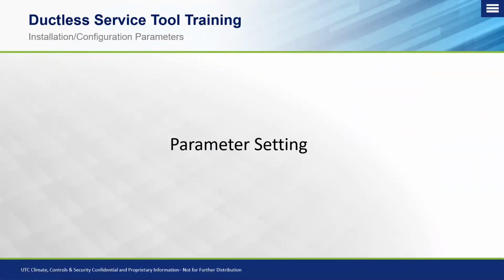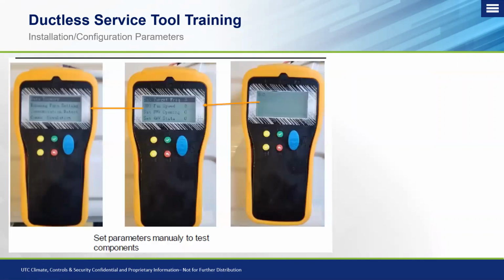Okay, so now moving on to your parameter setting. So your parameter setting on there is going to be done with your 5-volt connection. So if we kind of backtrack a little bit just to clarify on the information inquiry. The information inquiry, you can get information off of the LN and S connection and also the 5-volt DC connection. It just depends on where you want to plug in. With this particular parameter setting, you want to plug in on the outdoor unit if you're trying to test individual components with your 5-volt DC connection.